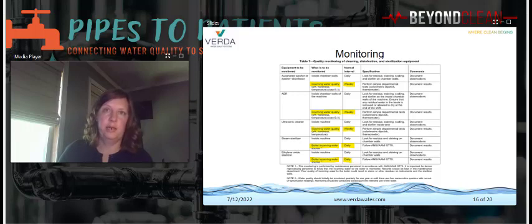Table 7 from AAMI TIR 34 describes visual observations that should be made by device reprocessing personnel on a routine basis, in many cases daily. The quality of water is important at each stage in the process and needs to be monitored. Table 7 lists weekly measurements of pH, hardness, and temperature for incoming water to automatic washers, washer disinfectors, AER, and ultrasonics. Note that the table also recommends observations or measurements be documented. Documentation is important to verify that the monitoring is done, to establish trends, and to indicate problems.